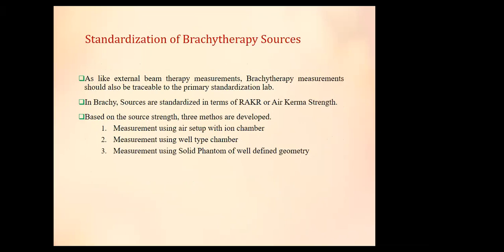Standardization of brachytherapy sources: as with external beam therapy measurement, brachytherapy measurement should also be traceable to the primary standardization lab. In brachytherapy, sources are standardized in terms of reference air kerma rate or air kerma strength. Based on the source strength, three methods have been developed: measurement using an air setup with an ion chamber, measurement using a well-type chamber, and measurement using a solid phantom of well-defined geometry.